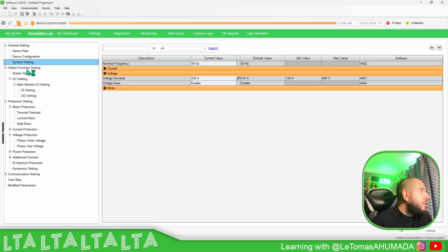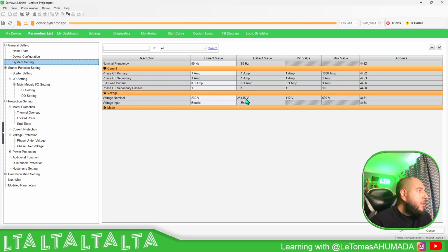As you saw in my case, I haven't defined this part, so of course there's going to be some troubles. And maybe this one should also be checked, but you saw that it's very straightforward once you know the right configuration for the motor, the protection you need to have, and the IOs that you're going to use. That's everything in the manual, so everything is there. So this is how you can make the direct online using the TeSys Tera. You saw it's very simple.